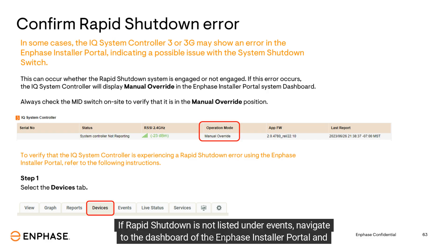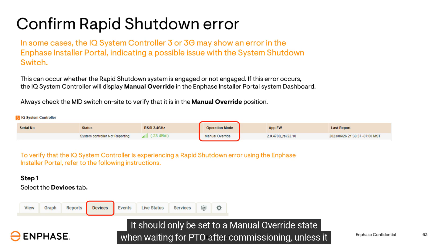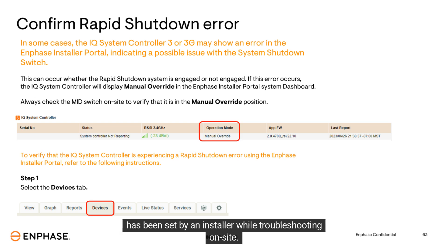If rapid shutdown is not listed under events, navigate to the dashboard of the Enphase installer portal and check the IQ System Controller operation mode. It should only be set to a manual override state when waiting for PTO after commissioning, unless it has been set by an installer while troubleshooting on site.